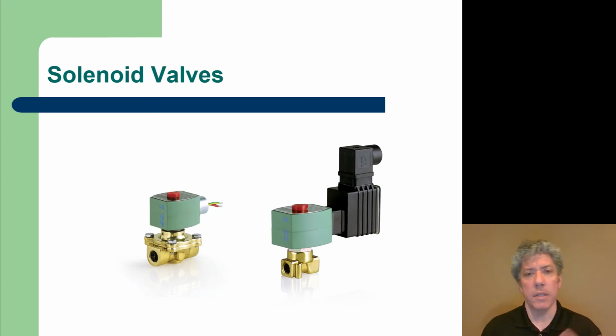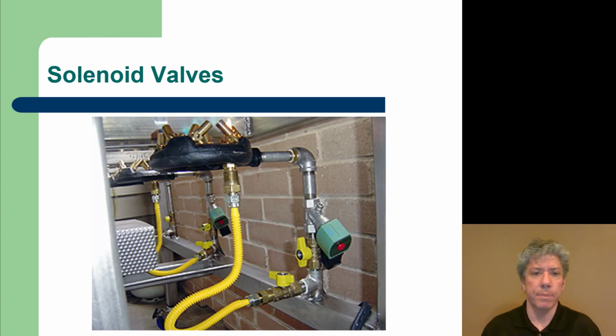Now, an interesting thing about that is that in the past, these have only been used for on-off control. But ASCO came out with a product about the time I was working for Amatrol, which was, oh goodness, 2007, I guess, was the last time I was there. And they came out with these valves a few years before I left, so probably in the 2004-05 range, something like that. And rather than the valves being completely on or off with the spool being moved completely to either position, they applied a varying electrical signal to the solenoid itself in order to float the spool. And so the spool could control the valve and move the valve stem in and out to any position desired. It was a relatively inexpensive and pretty clever little control device.